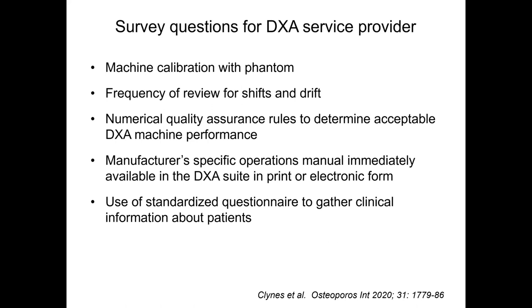For the service provider, we have three sets of questions. The first looked at machine calibration with the Phantom, the frequency of review for drift, numerical quality assurance rules to determine acceptable performance, and manufacturer's SOP manuals immediately available in the suite in print or electronic form.